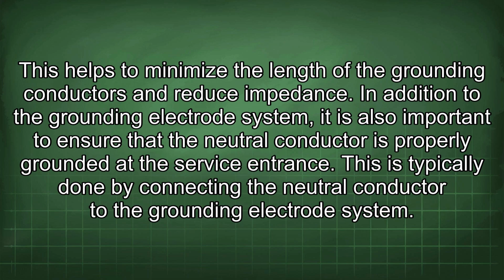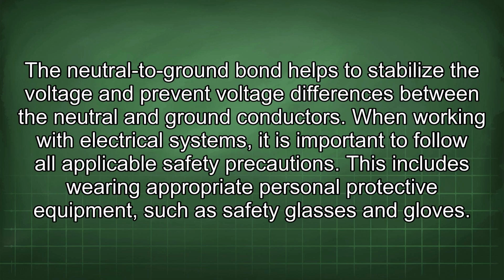In addition to the grounding electrode system, it is also important to ensure that the neutral conductor is properly grounded at the service entrance. This is typically done by connecting the neutral conductor to the grounding electrode system. The neutral to ground bond helps to stabilize the voltage and prevent voltage differences between the neutral and ground conductors.